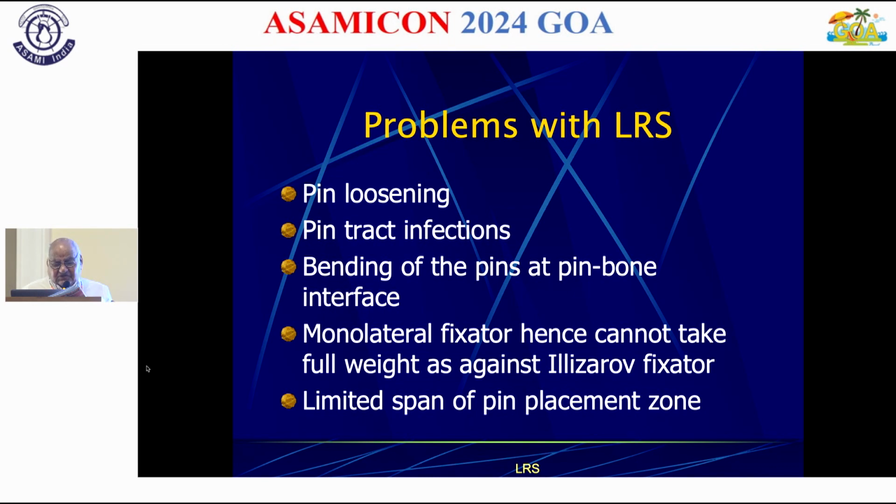Problems with LRS are that sometimes pin loosening occurs, pin tract infection occurs, and bending of the pins at the pin-bone interface. A monolateral fixator hence cannot take full weight, as against the Ilizarov fixator. There is also a limited span of pin placement zone in LRS.